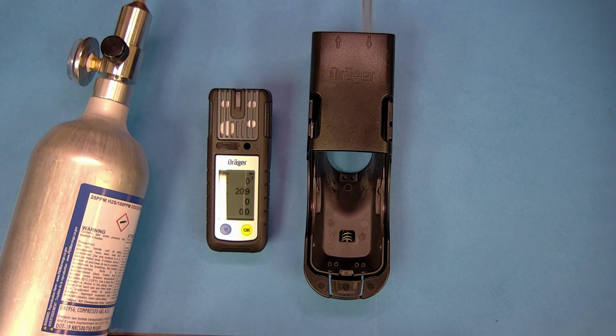Bump testing can take place manually, in a bump test station, or on the Draeger X dock. Today we will discuss the manual process. There is a manual procedure to complete a bump test that does not record the event as a completed bump test, but rather as an alarm event in the data logger. This is not the preferred way to do a bump test. We're going to be going over the preferred method.